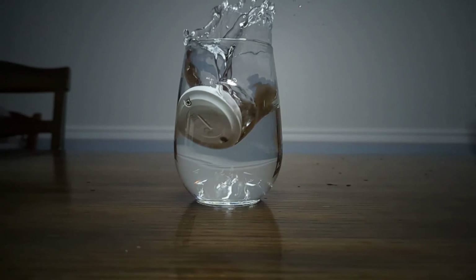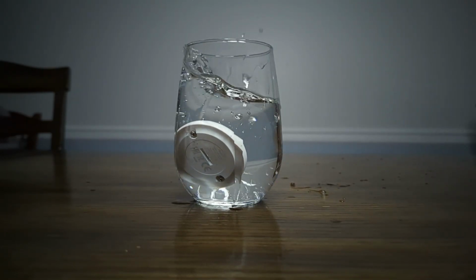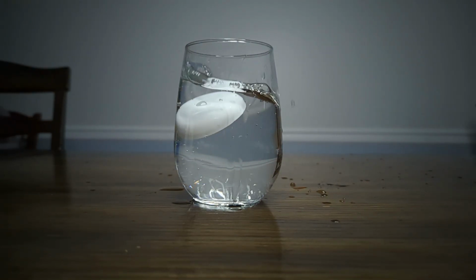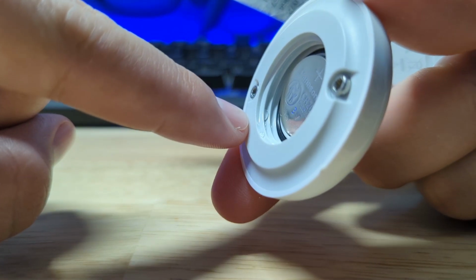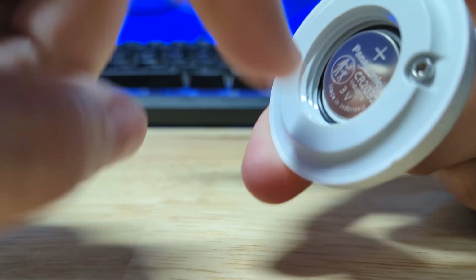I put the sensor in a bowl of water for 24 hours, and when I took the battery cover off, there was some water that had worked its way down a few thread lengths, but it hadn't even gotten to that O-ring seal.